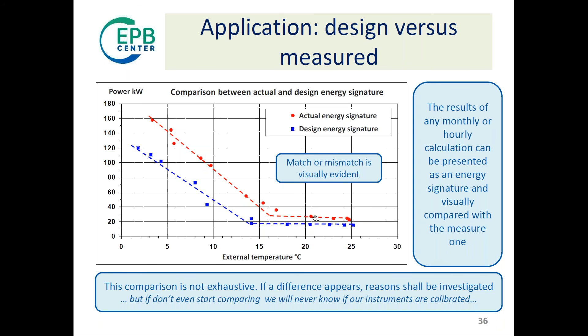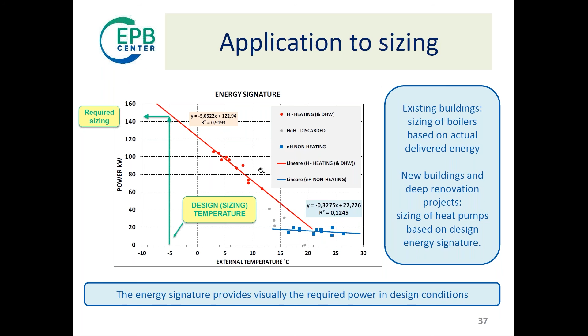Another application: if you have your energy signature, you have one important piece of information - here you can read the power needed by your building in design conditions. That's very effective when sizing a boiler for a renovation. You could do the same with the design energy signature to get information for sizing your heat pump, which is a much more interesting way of sizing a heat pump by leveraging information from the energy performance calculation - and this helps avoid a lot of oversizing.